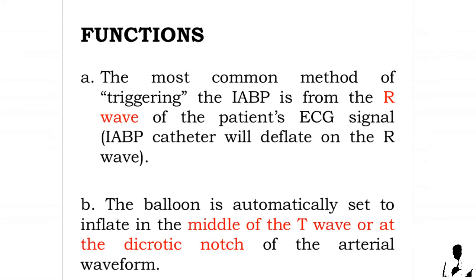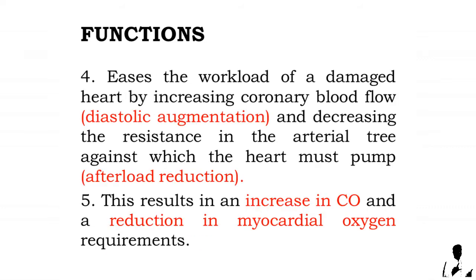The most common method of triggering the intra-aortic balloon pump is from the R wave of the patient's ECG signal; the IABP catheter will deflate on the R wave. The balloon is automatically set to inflate in the middle of the T wave or at the dicrotic notch of the arterial waveform.